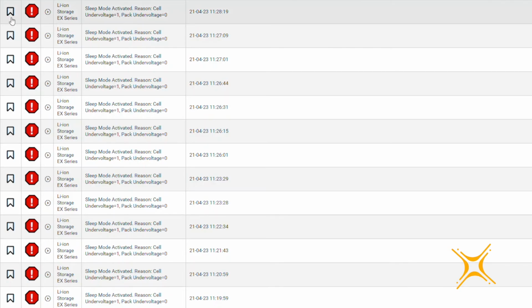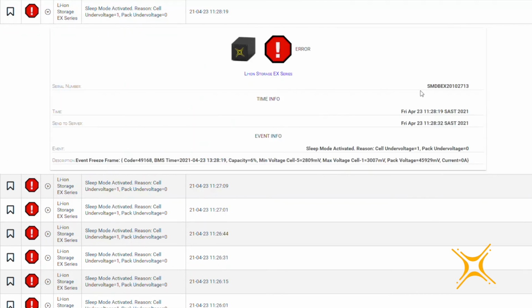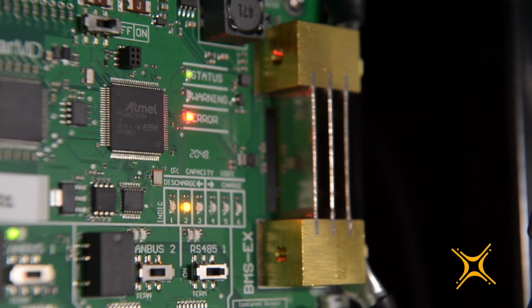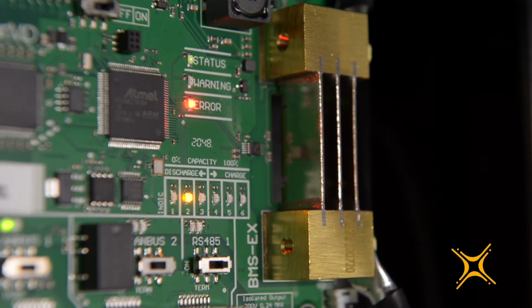For each event generated, a freeze frame is stored, showing the exact battery conditions such as serial number, date and time, voltage, current, capacity, and temperature at the time of the event. Indication LEDs. The BMS also uses indication LEDs on the board as well as the LEDs on the multi-function push button to display warnings and errors. You can refer to the manual for a complete list of warnings and errors to diagnose any problems locally.